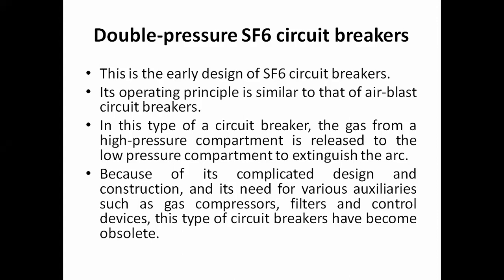The working principle of this type of circuit breaker, that is the SF6 circuit breaker, is exactly the same as the air blast circuit breaker. Whenever a fault occurs in the system, the moving contact has to be separated from the fixed contact with the help of a spring mechanism, that is, the electromagnetic coils get energized and try to move the moving contact apart from the fixed contact. Due to the high voltage, that is the potential difference, an arc is struck between the fixed contact and the moving contact, and you have to extinguish the arc.